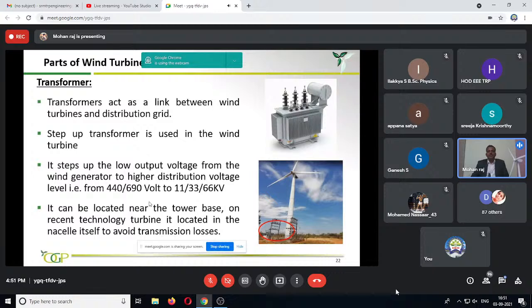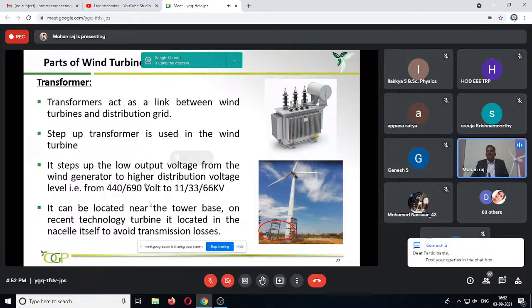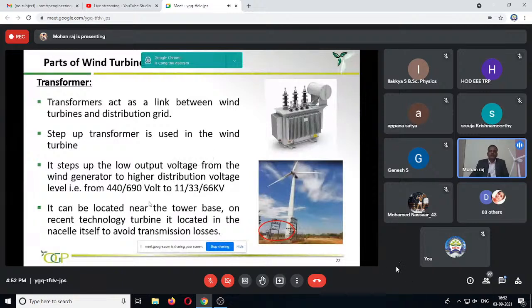So normally in a wind turbine, the generator will generate a voltage of 440 volt. A 440 volt generator is available, and 690 volt is also available. For higher rated wind turbines, 690 volts are available. So we cannot synchronize 690 volt to the grid, and we cannot pump low voltage power over a long distance. That's why we need to step up the voltage. For that purpose, a step-up transformer is used in the wind turbine. Normally, it is mounted at the bottom of the wind turbine, but in recent days, to avoid the transmission losses between the nacelle and the bottom, they are mounted at the top in the nacelle itself.